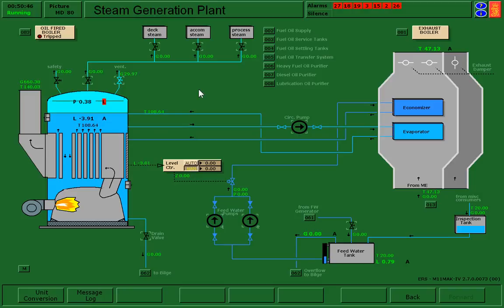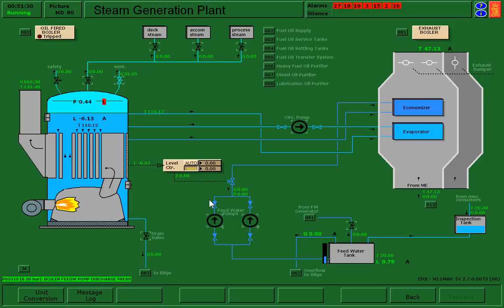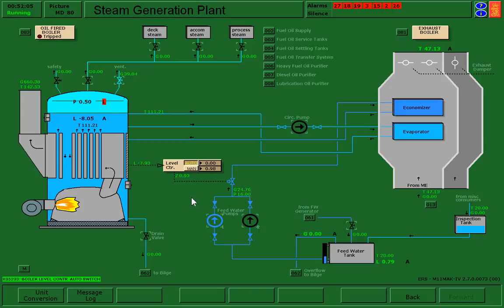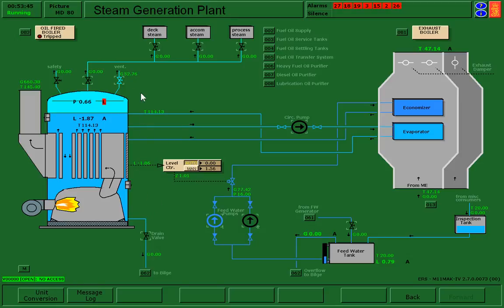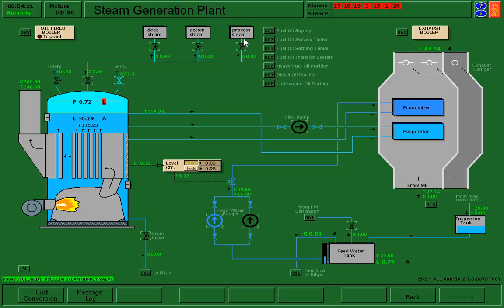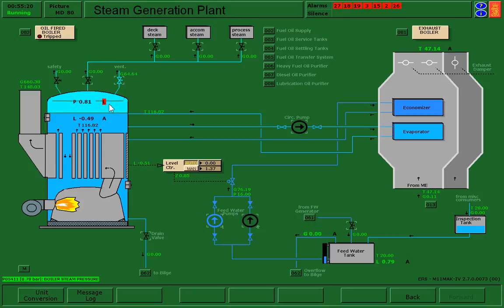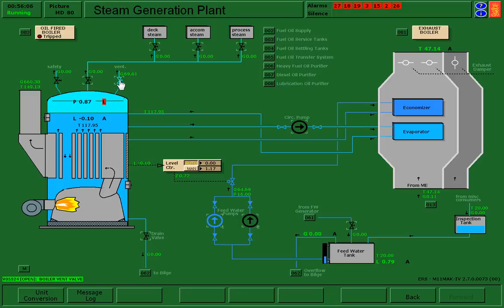At this point, a couple things we're going to do. Now that we're up to pressure and we have a bit of time, we could start to get our pumps back on because we know we're going to need them. So you can turn on a feed water pump and switch over your level controller to automatic, and that should keep you stabilized around zero. If you were a long way off, you might want to manually put water in first before you switch over to auto with your pump on. Rule of thumb that we use here is we're going to wait till we have a bar of pressure that we've built up before we close our vent. So once we get to one, that's when I'm going to close my vent.